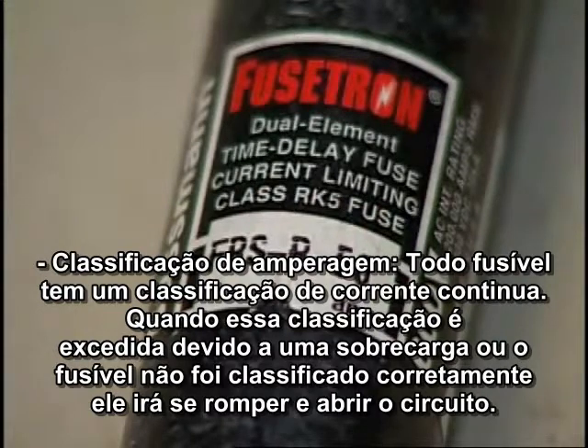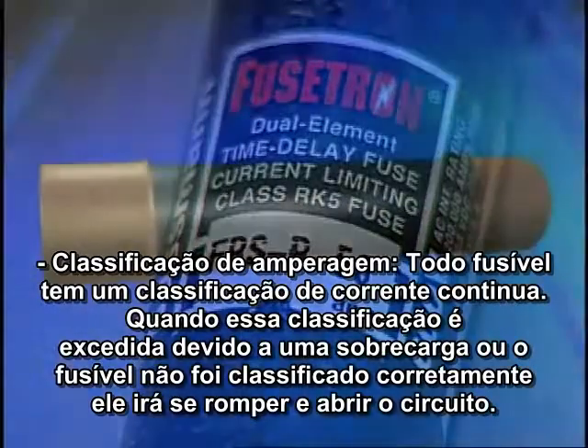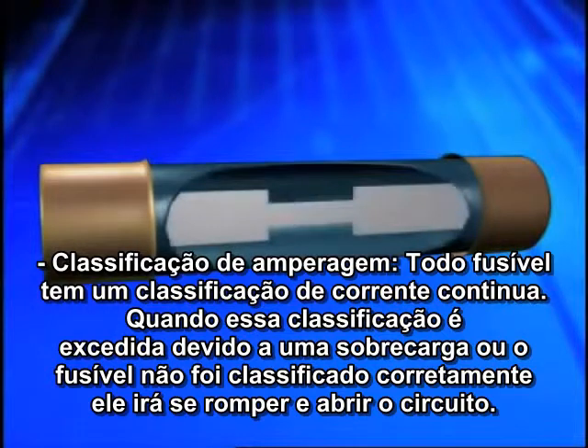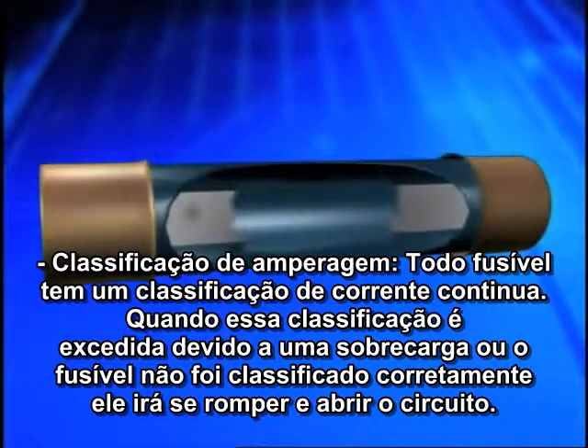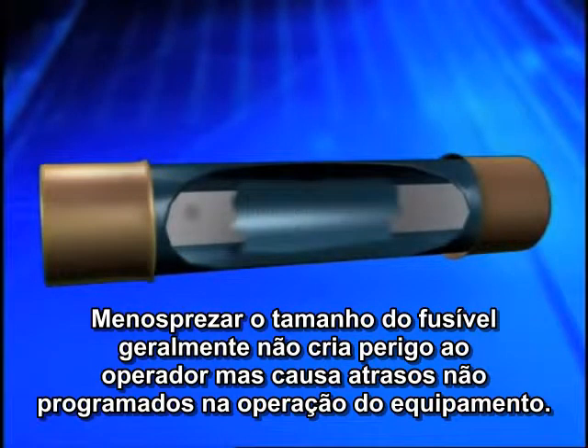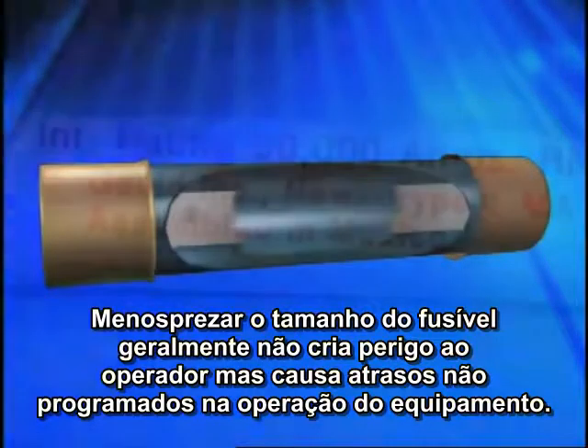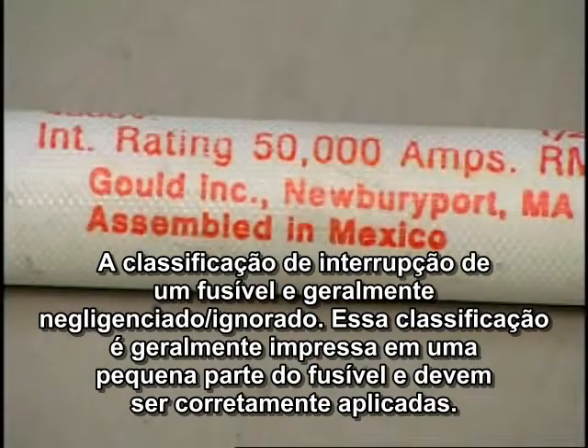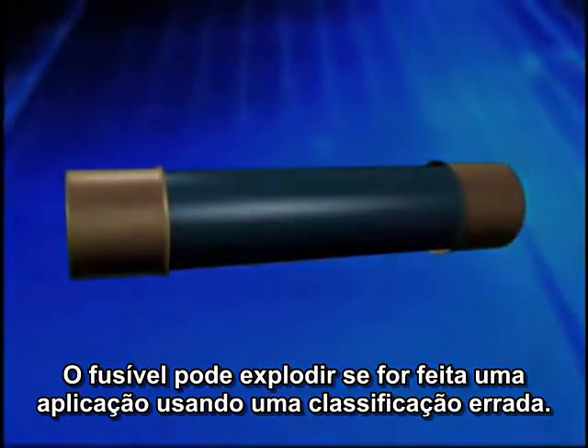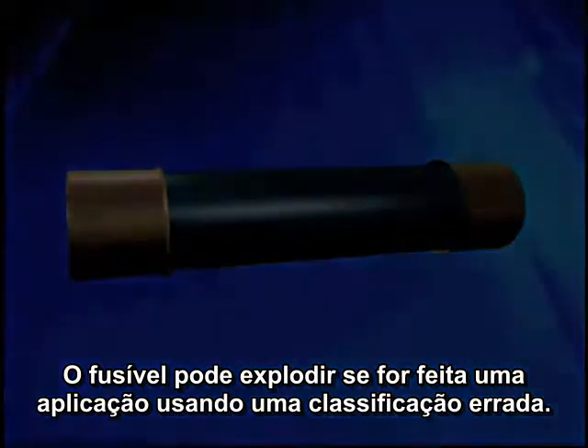Ampere rating. Every fuse has a continuous current rating. When this rating is exceeded due to overload or because the fuse was not rated properly, the fuse will blow and clear the circuit. Underrating the fuse size usually does not create a hazard to personnel, but does cause unwanted delays in the operation of the equipment. The interrupting rating of a fuse is often overlooked. Interrupting ratings are generally printed in small print on the side of a fuse and must be properly applied. A misapplied fuse with an incorrect interrupting rating could explode.